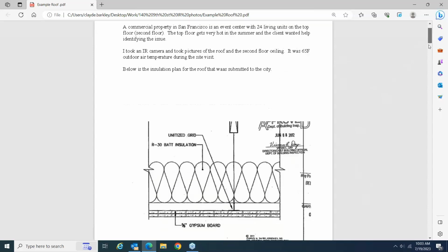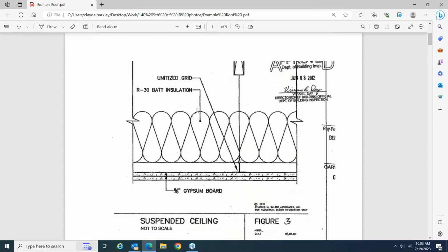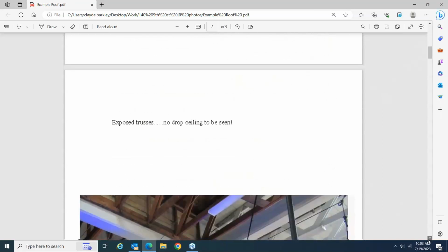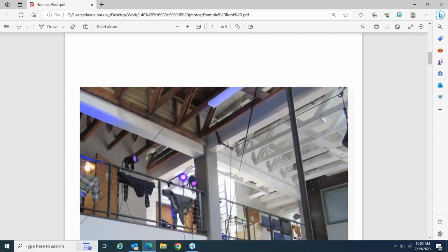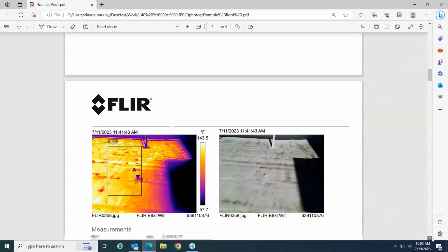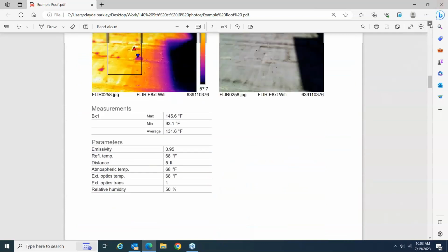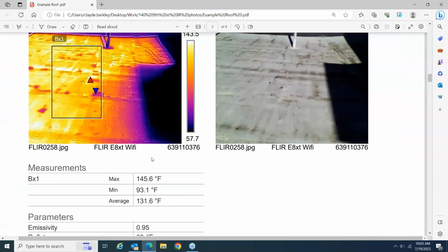It was 65 degrees when I was there. That's not very hot. And I asked for drawings ahead of time, like you always do, and the drawings called out R30 batt insulation and a couple of 5/8 gypsum board ceiling. I was like, okay, well, I got there, and this is their ceiling. It's just exposed truss. There is no gypsum. There is no insulation. So I headed up to the roof, and they have the asphalt rollout type. And the average was 131 degrees on the roof.